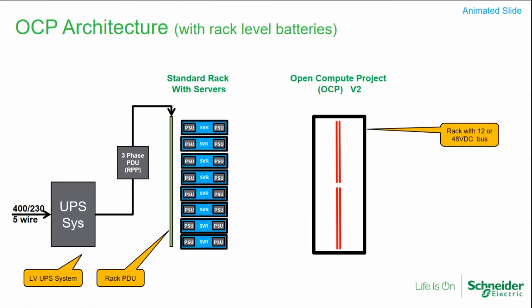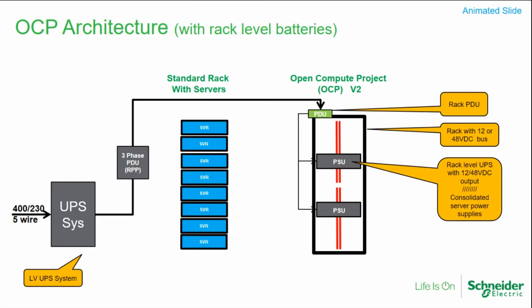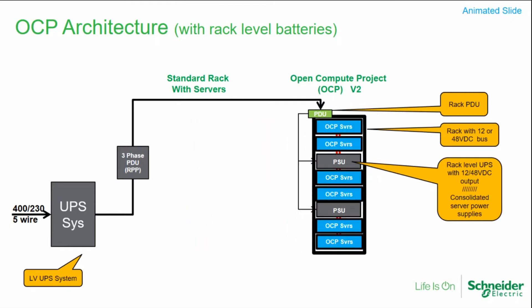What's different with OCP: instead of 19-inch between the rails it's 21 inches, the PDU goes away, and power is distributed to each server via bus bars in the back at 12 or 48 volt DC. These power supplies are no longer in the servers — they're centralized — and AC comes into them through a rectifier that gives you 12 or 48 volts DC. Whereas each server previously had two power supplies for redundancy, they now have none, all centralized at the rack.